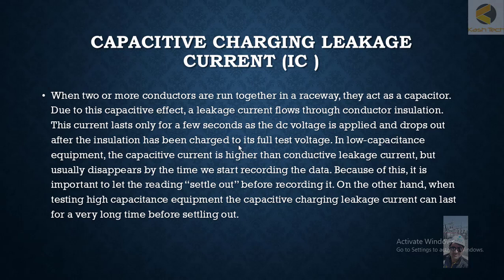In low capacitance equipment, the capacitive current is higher than the conductive leakage current, but it usually disappears by the time we start recording data. That is why we always wait for the reading to be stable — because at that time the equipment keeps charging and you are not able to get a real reading. It is important to let the reading settle out before recording it.